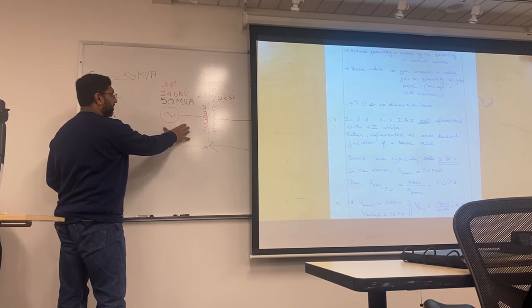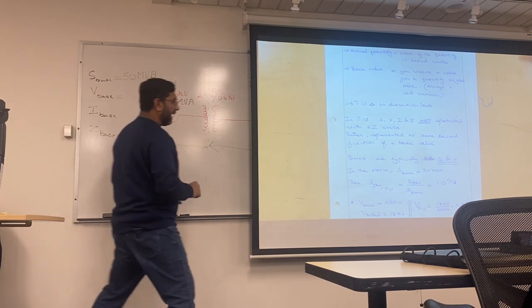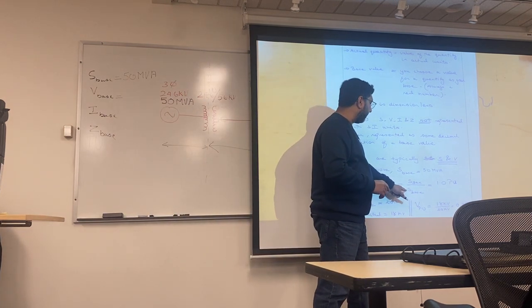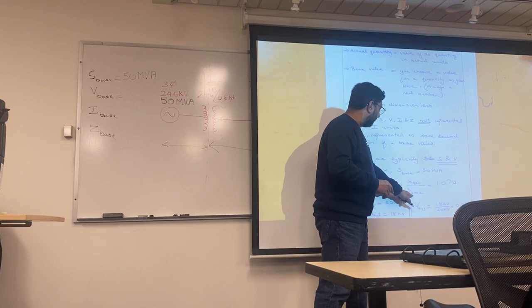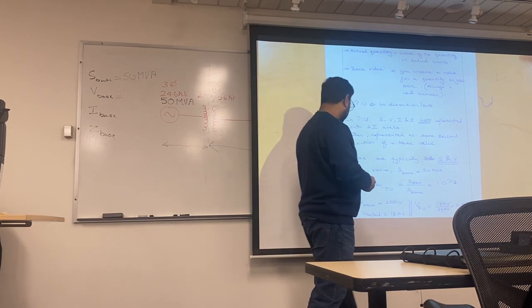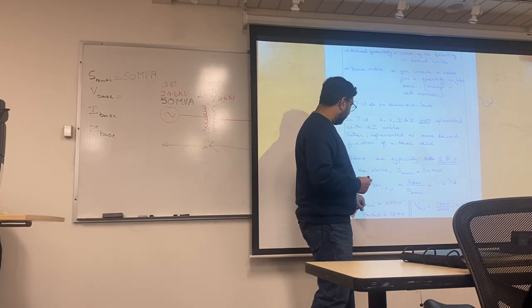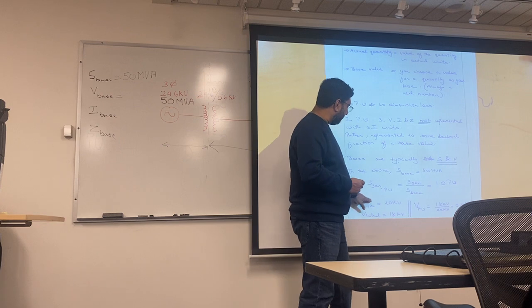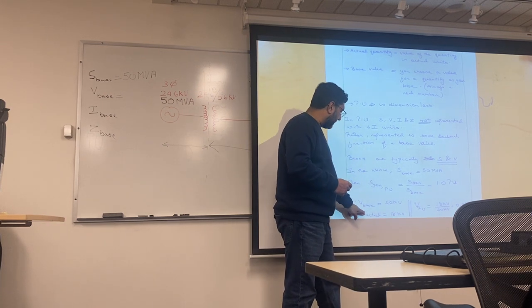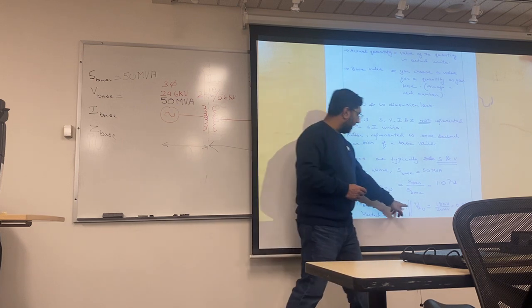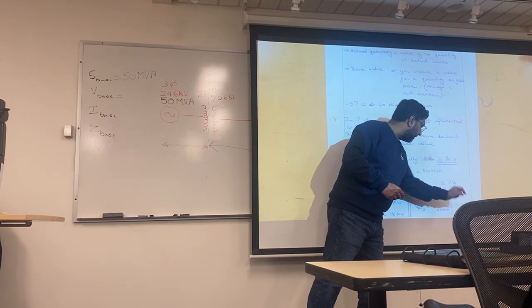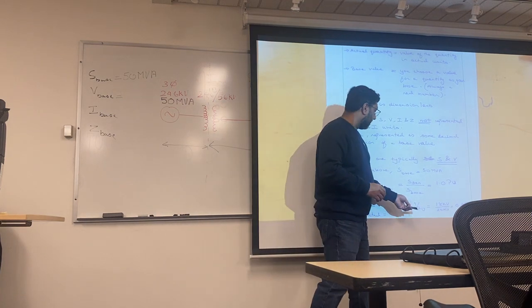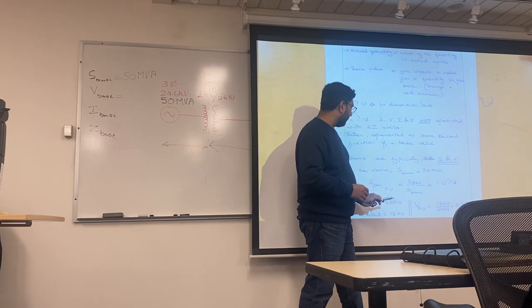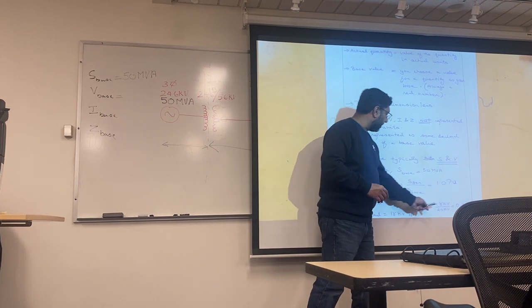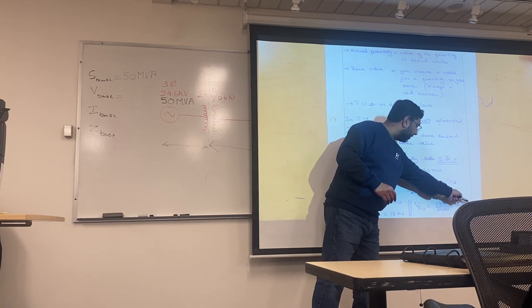If I had a second generator here with 45 MVA, keep in mind my S base doesn't change for the entire system. It would have been 45 divided by 50, a different PU. And I had a voltage example where I picked my V base as 20 kV, and let's say there's equipment rated for 18 kV. My V-PU would be 18 kV divided by 20 kV, which is 0.9 PU. Again, keep in mind, you have to show voltages here because those are the quantities, but once you go through your math, you end up with just a ratio, and you call it a PU, per unit.